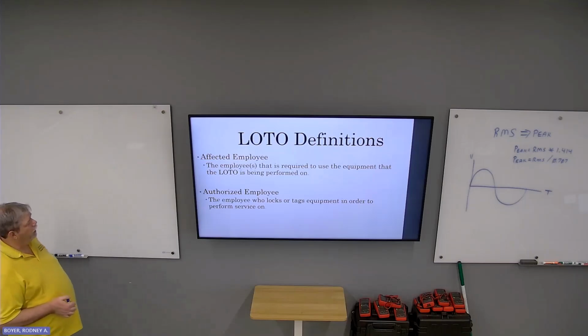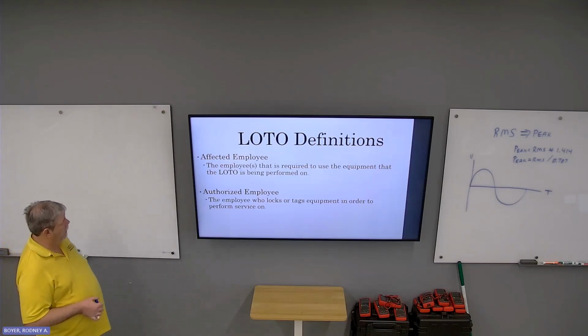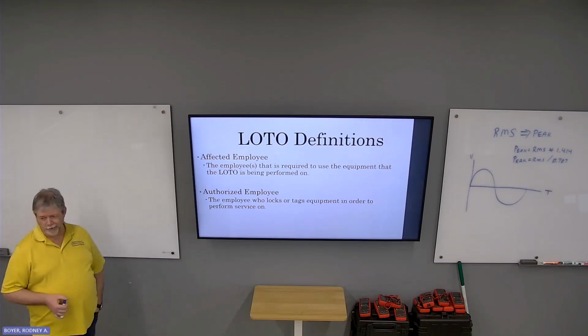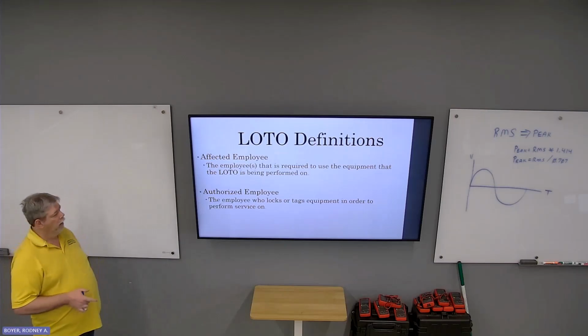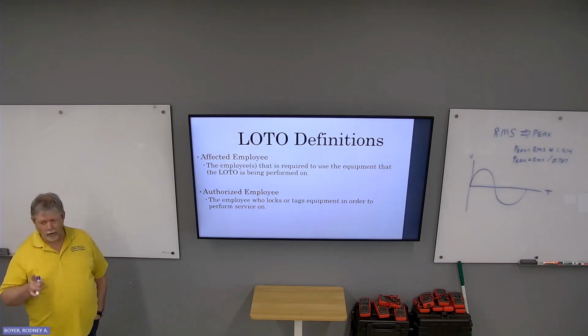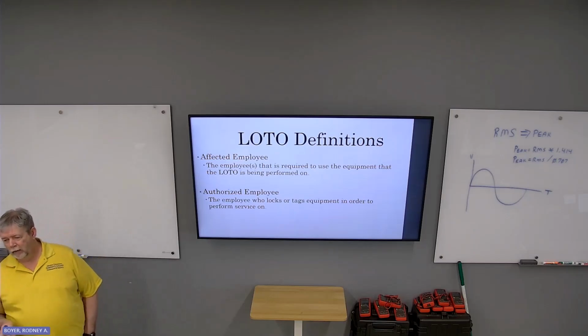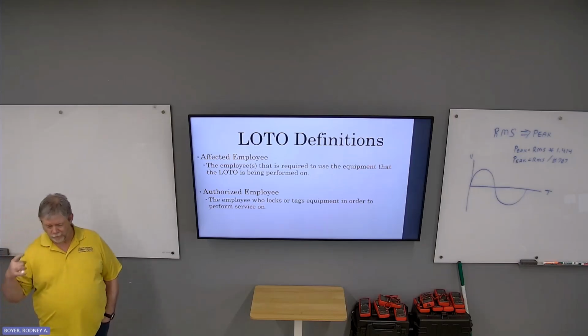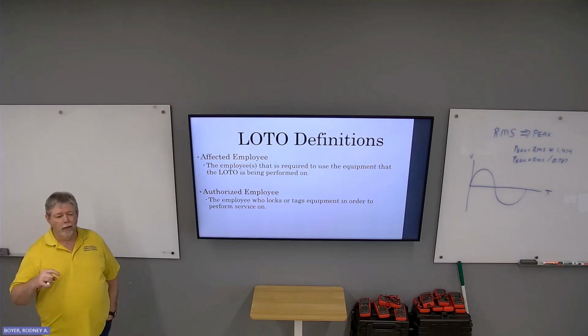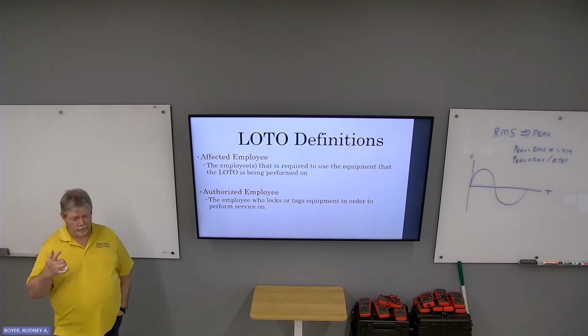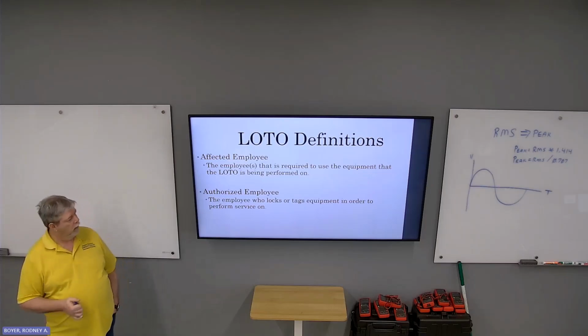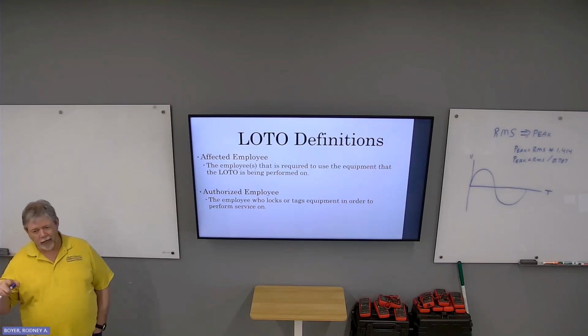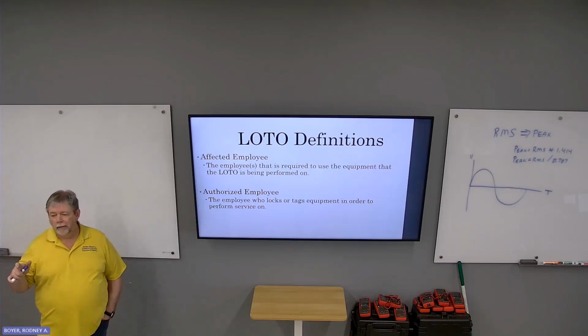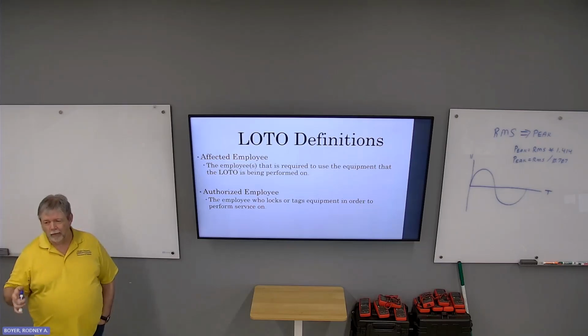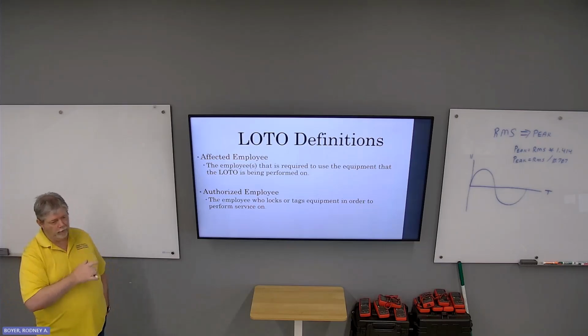An authorized employee is one who locks or tags equipment to perform that service. Authorized employees are the only ones allowed to put the lock on, because there's a very specific sequence of steps to ensure energy is isolated and dissipated, and not just anybody is trained to do that. Everybody has to be trained as an affected employee, while those doing the locking out and tagging out have to be trained as authorized.